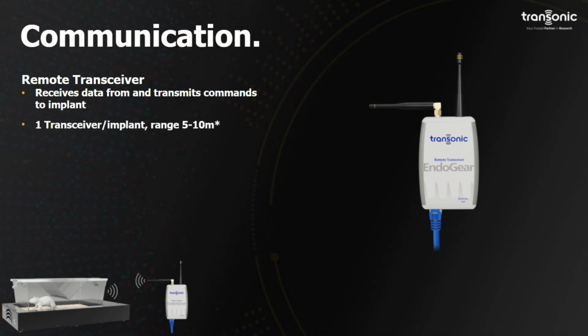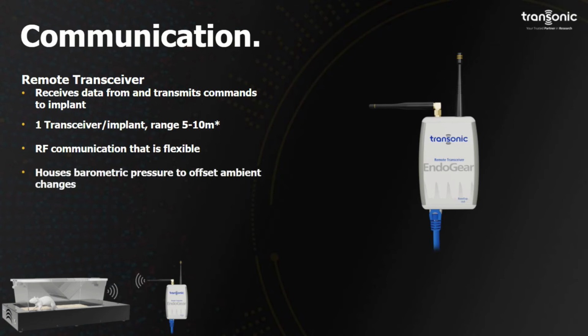This is designed as a 1-to-1 ratio, so each implant requires one transceiver. It's RF communication that is flexible, meaning you can change frequencies. It also houses a barometric pressure sensor to offset ambient pressure changes.